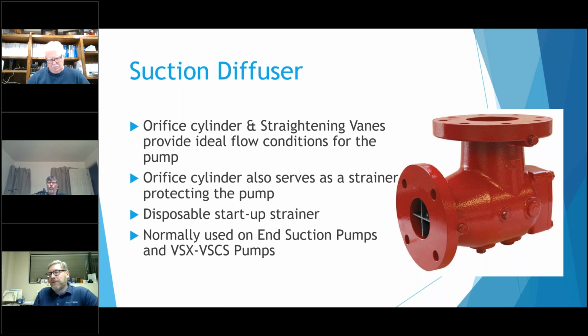But you should be able to reuse it if you carefully pull that off, pull the cylinder out, and then pull that startup strainer. It's just a little brass strainer material. A lot of people hang them up and say, hey, I made sure I took it out, but in the end, it just gets thrown away. If it's an older system, there still could be a lot of junk in there, so maybe monitor that, go back, pull it out and see what's in there. But certainly on newer systems, you can get a lot of junk that it collects, so it doesn't go into the pump and damage the seals or other components of the system.